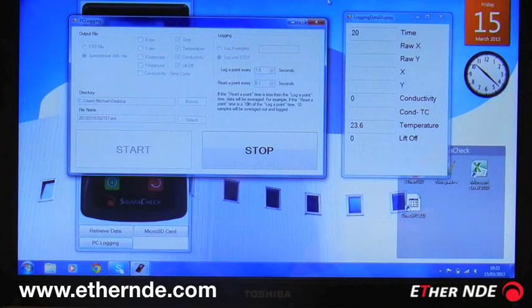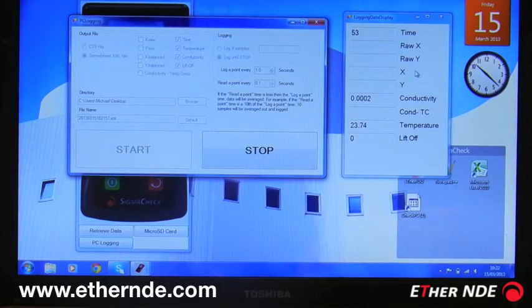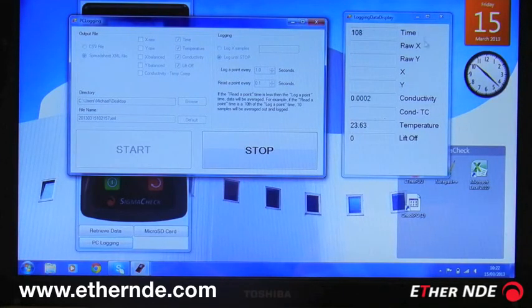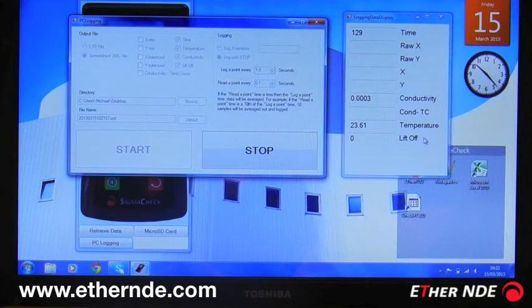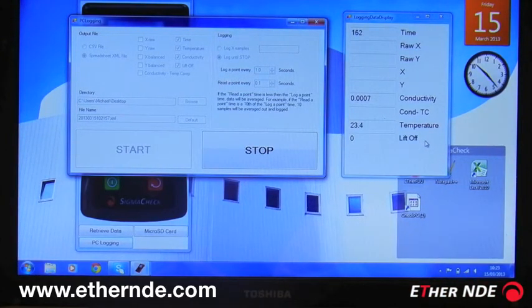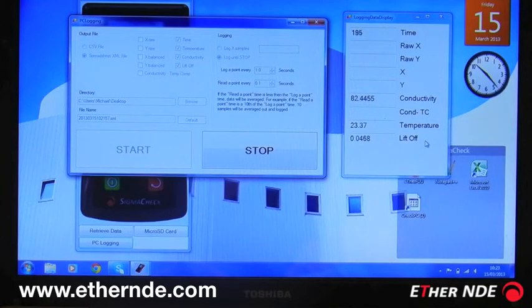So I shall click start. Now on this display, each time a data point is logged, the values are displayed in real time here. As I specified, we're logging time, conductivity, temperature, and liftoff once a second.